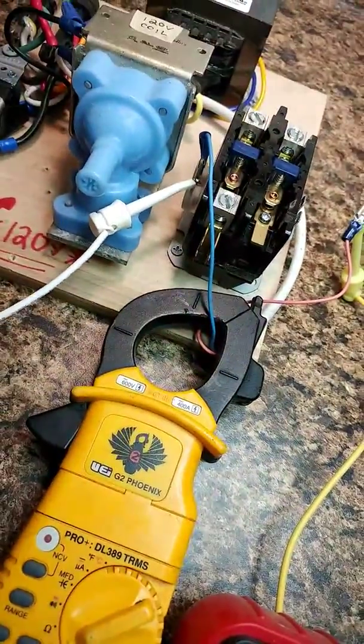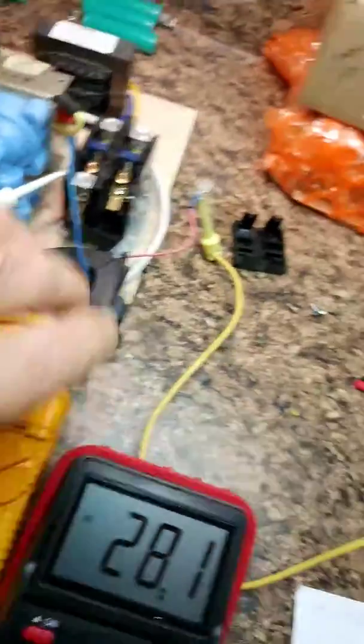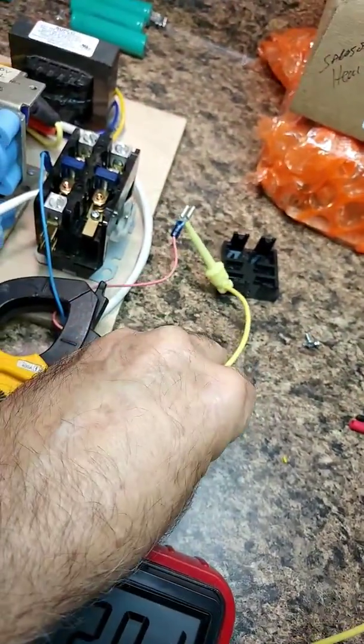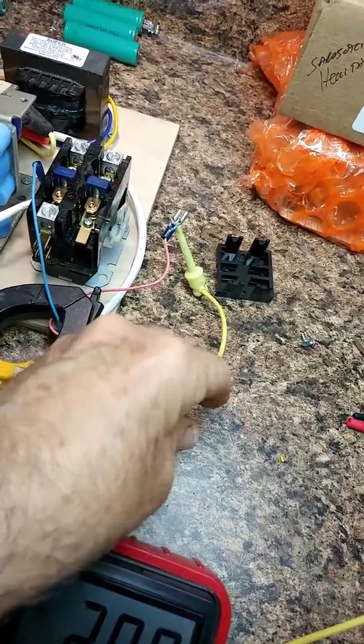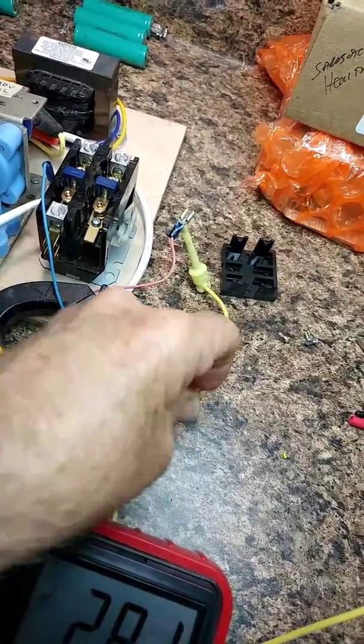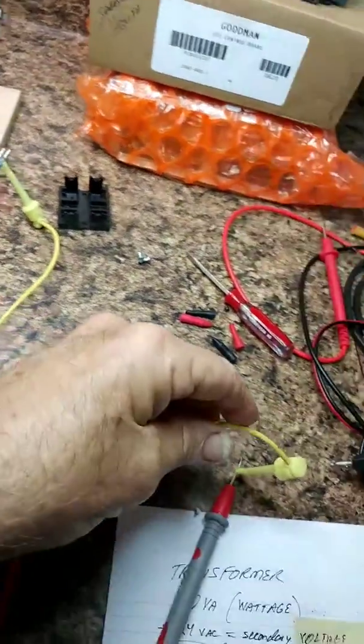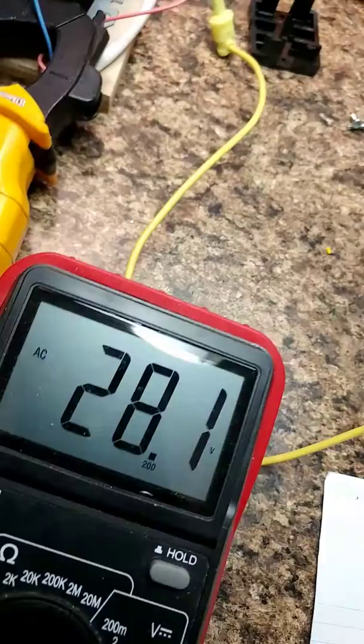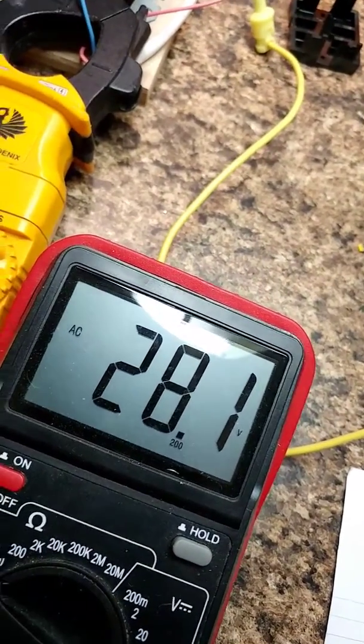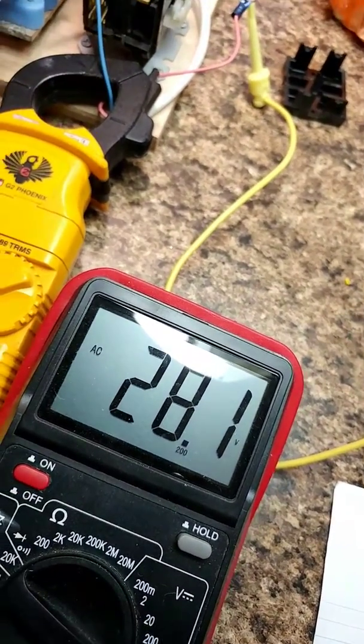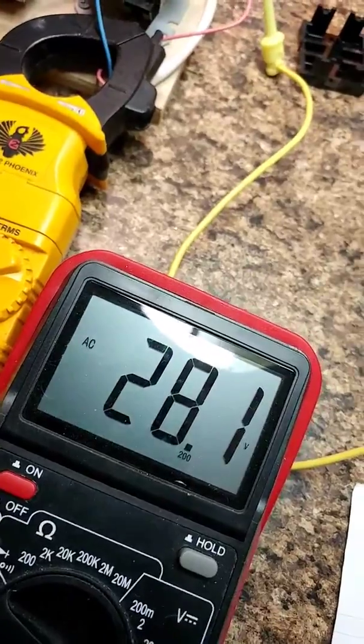So I've got my lead here coming off one side of my coil and what would normally be my Y signal coming off the other side to my other lead. So I'm checking my voltage, which is 28, which is a little high, I know, but usually it's about 24 to 28.